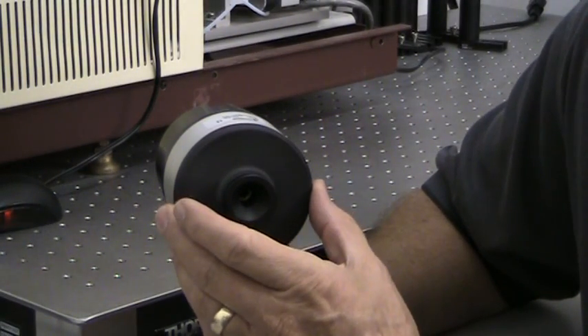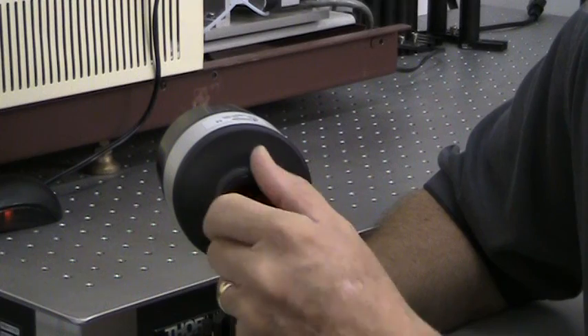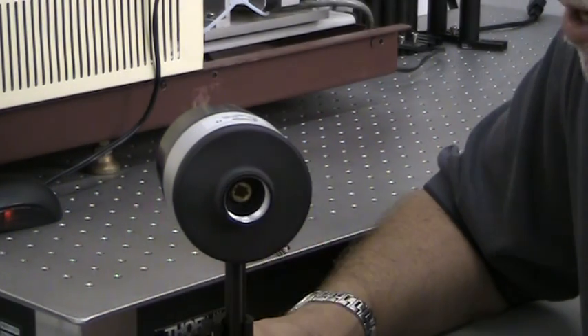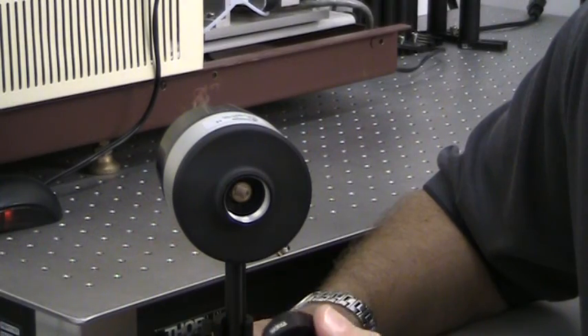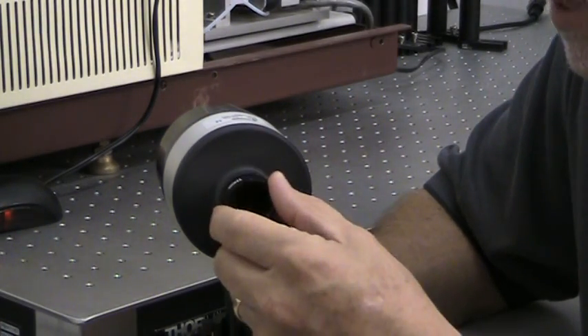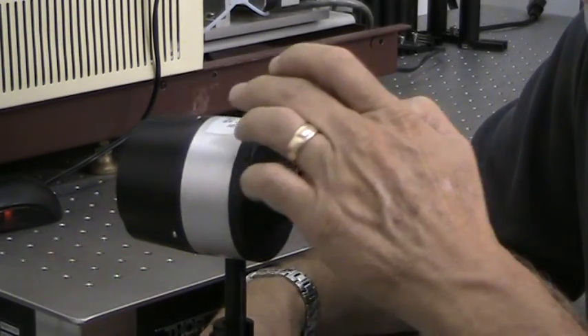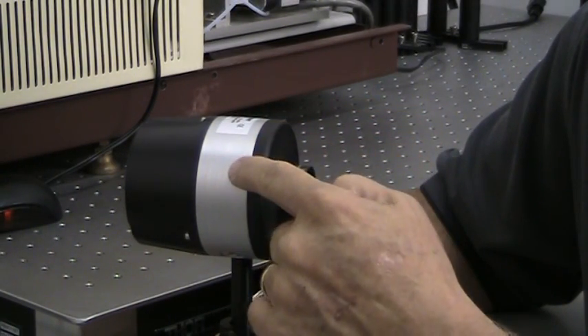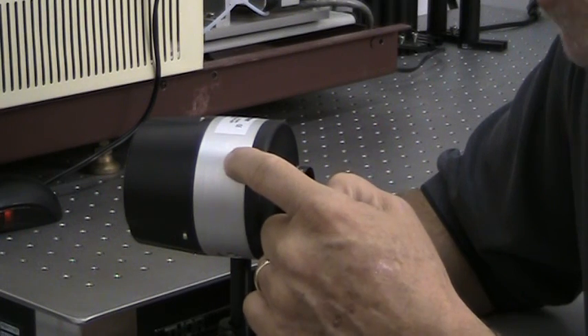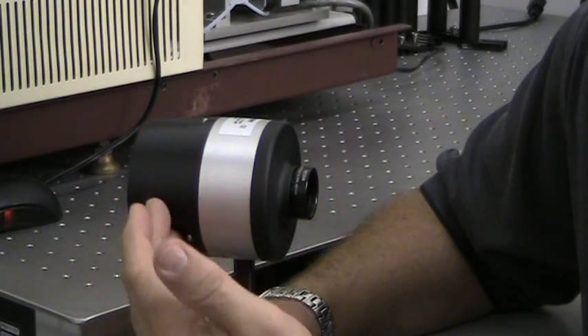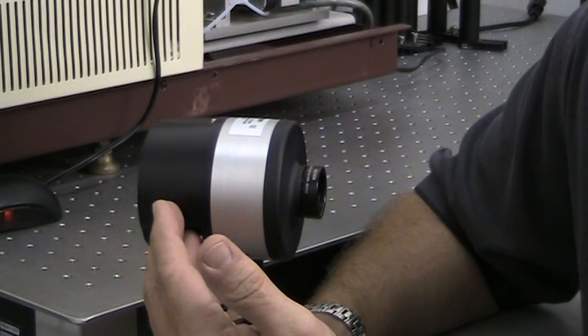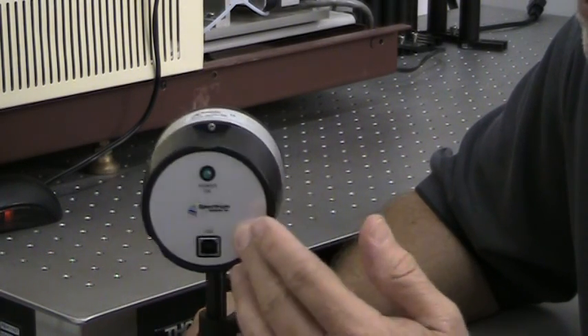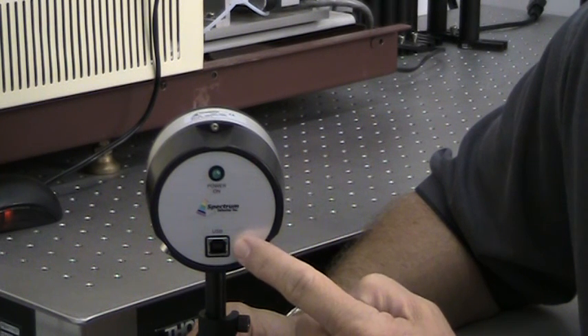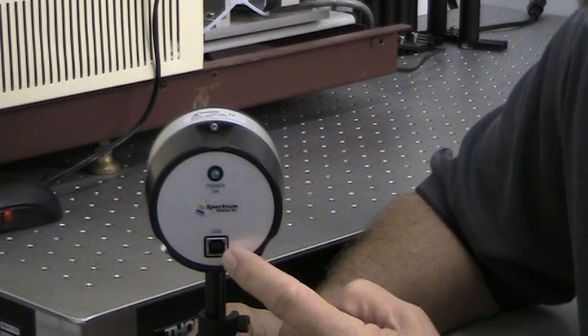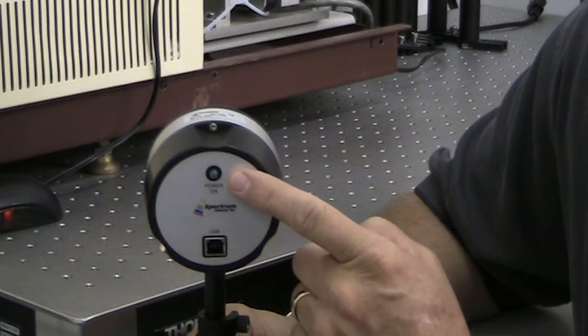Now let's take a closer look at the joule meter probe hardware. It includes a front bezel with a removable aperture, a SM1 threaded hole here that allows you to add optical accessories like an ND filter by simply screwing it in place. It includes the detector module, which has the detector, an integrating preamp, and the EEPROM, and that is connected to the back half of the instrument, which has the microprocessor-based digital electronics and a USB connector for both power and the communication with the computer. And this is a green power on LED.